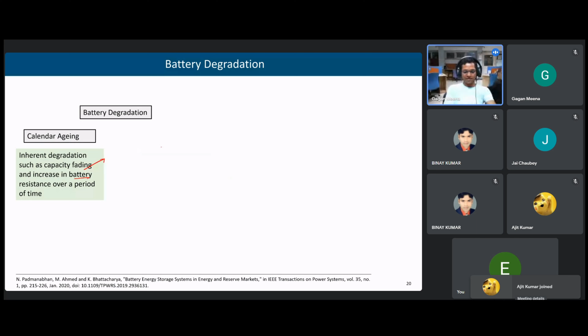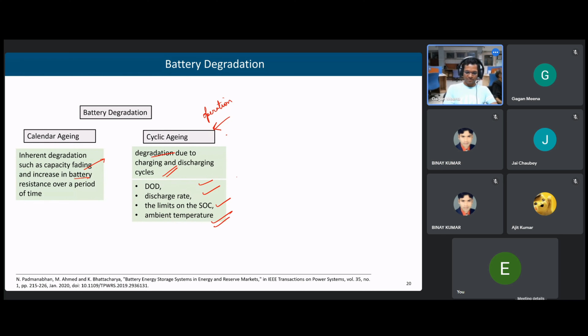This calendar aging is because of inherent phenomena, such as this - over time, batteries will inherently undergo degradation because of increase in battery resistance or capacity fading. Then another process is cyclic aging, which is due to operation - as the number of operations of the battery increases, the number of cycles of charging and discharging increases. That results in another kind of degradation called cyclic degradation, cyclic aging, and it depends upon depth of discharge, discharge rate, the limits on SOC, and the temperature also.